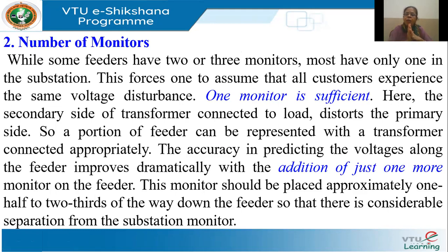The second issue is, how many monitors do I place? There are some feeders which have two or three monitors, and some feeders which have only one monitor at the substation. Actually, one monitor is sufficient to make an estimate. But sometimes there is a distortion on the secondary side of the transformer, which is connected to the consumer. You know that in a transformer, whatever happens on the secondary is reflected onto the primary, right? So if we add just one more monitor, then the estimation accuracy will improve. If I have a substation, I have a primary and a transformer, and the secondary is connected to the consumer.